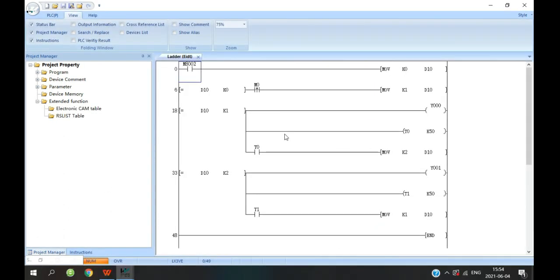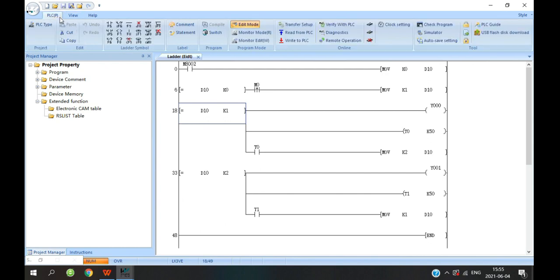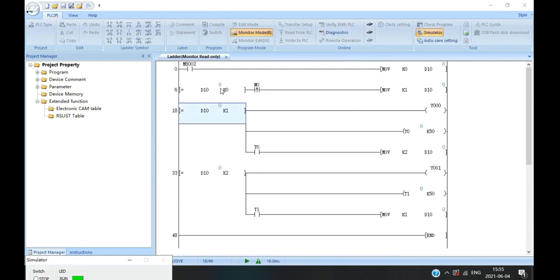And the second way is to use the LD= instruction. When you judge that the value of the D10 is 1, you will enter the first step. And then wait for 5 seconds, D10 is set to 2, and then you can enter the second step. And then wait for 5 seconds, D10 is set to 3.